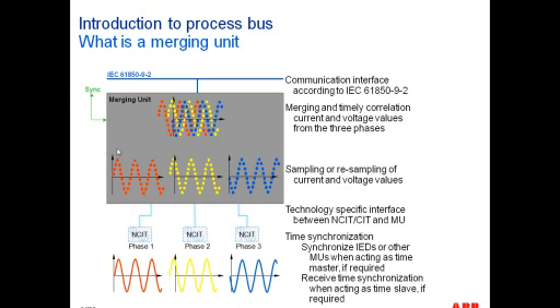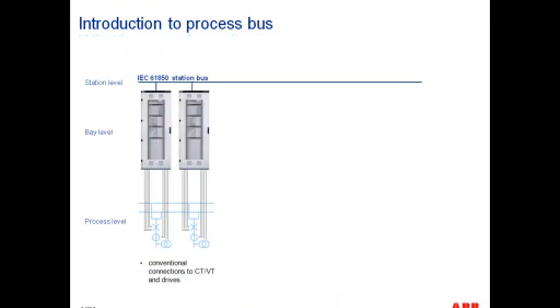One of the important considerations here is that if, let's say, in the case of a ring bus or breaker-and-a-half installation, you may have two merging units publishing information, but one IED that's subscribed to those two data streams, there needs to be synchronization, because obviously the signals need to be processed by the relay in a synchronous manner. And for that purpose, 61850-9-2 has a standardized format for how we're going to synchronize those signals. Essentially the signals are time-stamped with a definite time reference source that can be found inside of the substations. And we'll talk more about the specifics on that in a later slide.